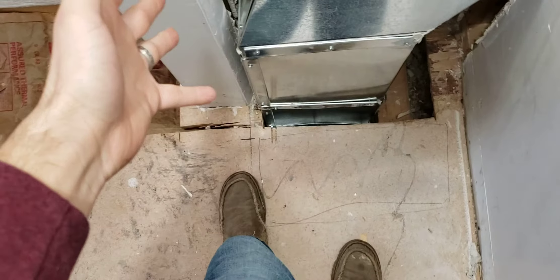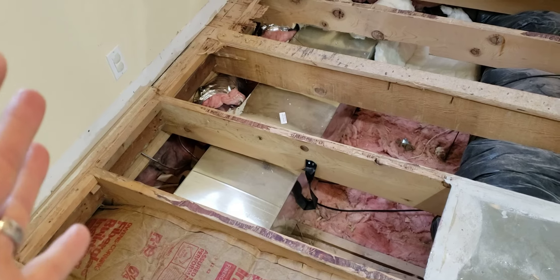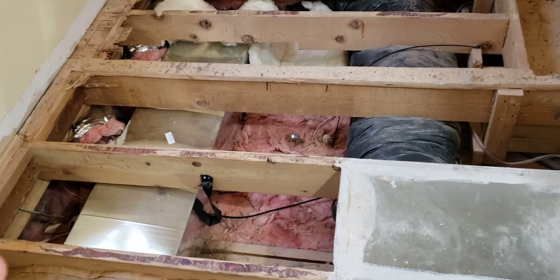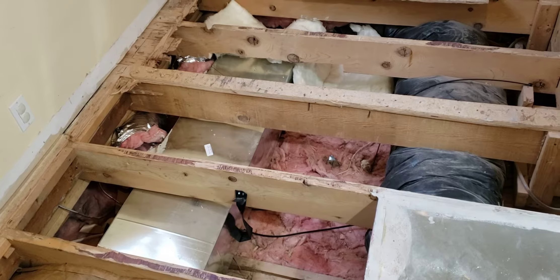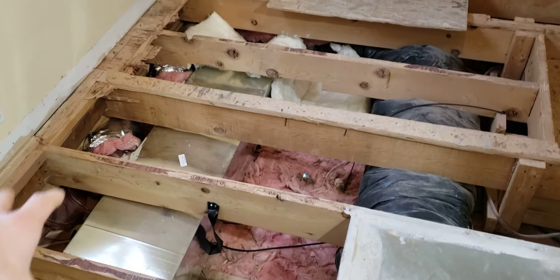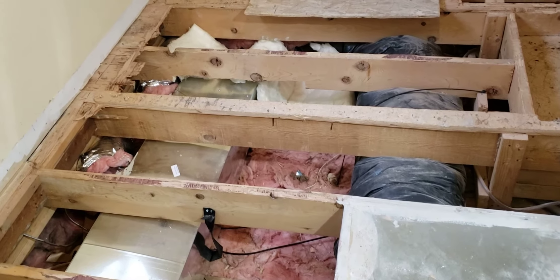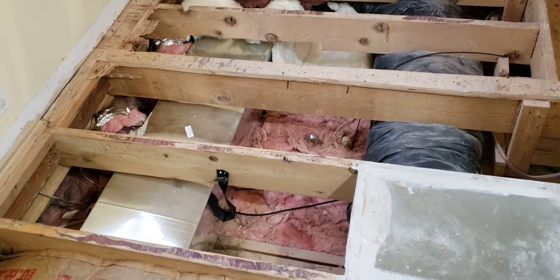We've talked specifically about sealing things up, and there's a flow issue downstairs, also a heat loss issue. Right now we are in January, and this was originally installed in March of last year. So just under a year, and they've had to come out four separate times adding more duct work, changing things around, changing the structure — and it's still not working. It keeps the house in the 60s at night.